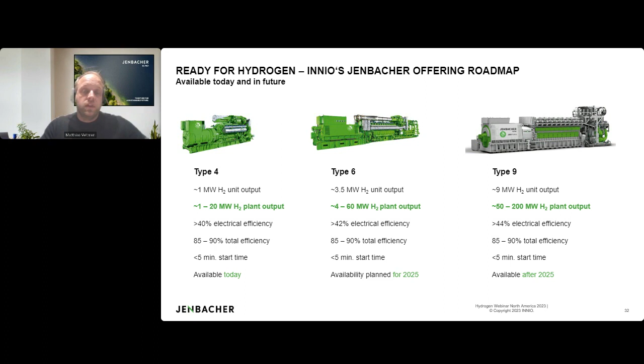So what to expect as we talk about the engines in a little more detail, specifically focusing on Type 4, 6, and 9 engines: Type 4 can handle power plants with an output from 1 to 20 megawatts on H2. Type 6, being a larger engine, enables us to go from 4 to 60 megawatts of power plant output, with a typical output here of about 3.5 megawatts. Our very large engine, Type 9, with expected 9 megawatt output on H2, would be for really large power plants with 50 to 200 megawatt power output. All of these have fast start capability, and specifically for Type 4, you already saw from Klaus that we are utilizing this in a data center application for backup power.